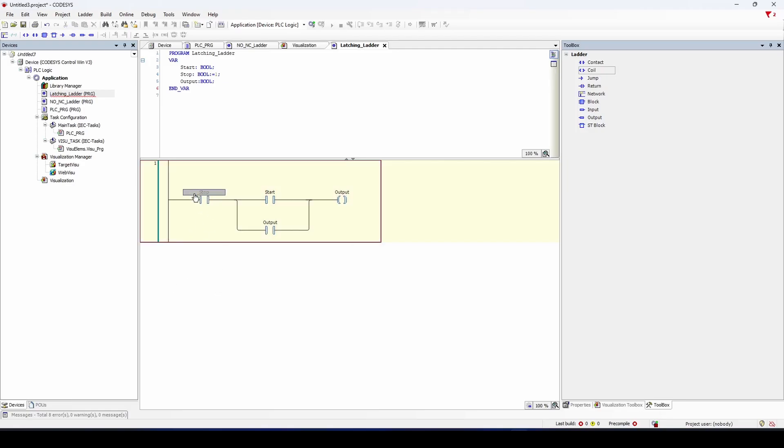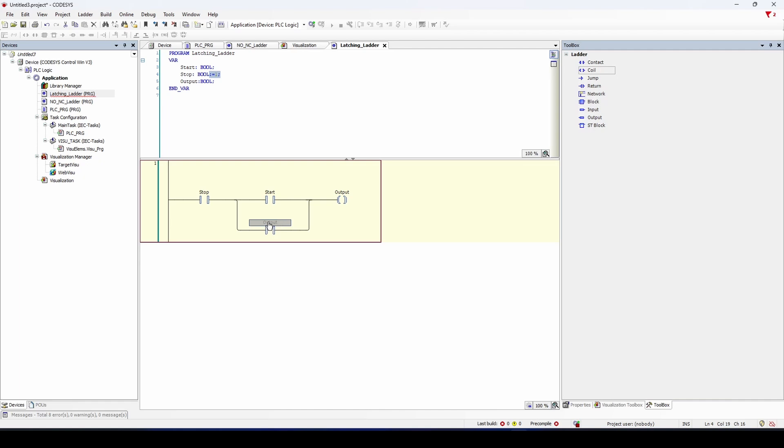So now our stop is going to be energized by default. That's when we set it to one. And then we'll be waiting for a start command to then latch this output as an on. And it'll latch because we're monitoring the output as a contact here. And so once it becomes a high, it becomes a one. We're going to have stop through the output and the output's going to remain on. But if we press the stop button, we're going to break that connection and everything is going to go to a zero state.